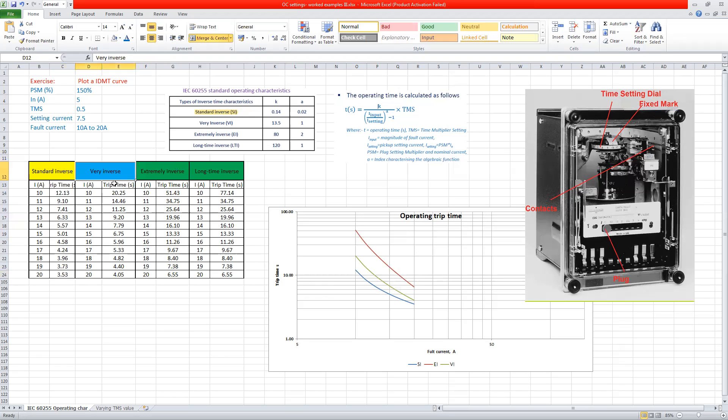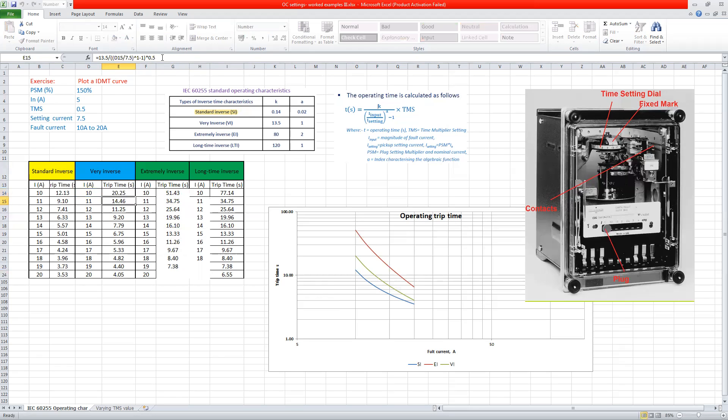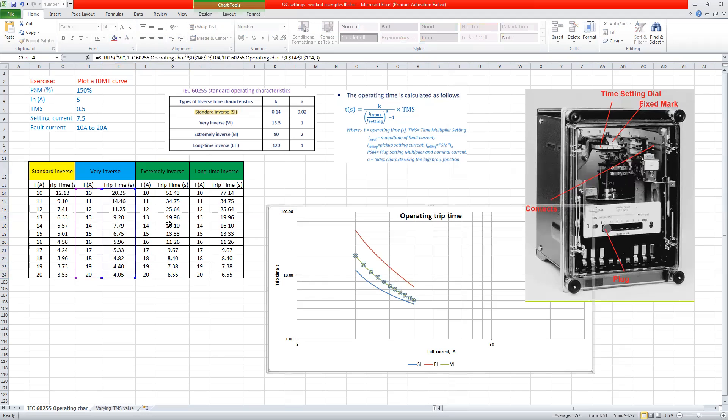Similarly, we can add for very inverse at 10. So we just have to arrange the formula. So for example, at very inverse, my K is 13.5. And then of course, A is not 0.02, it's 1. And then of course, the TMS is still going to start to fix it here. We set this here at 0.5. And then the similar relay, we can see the plots, this one on here, basically.